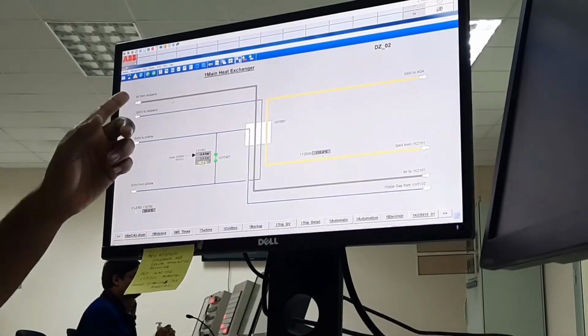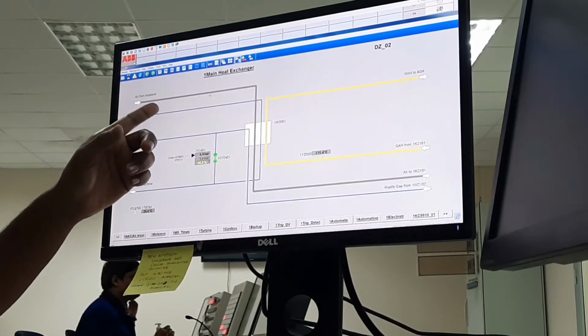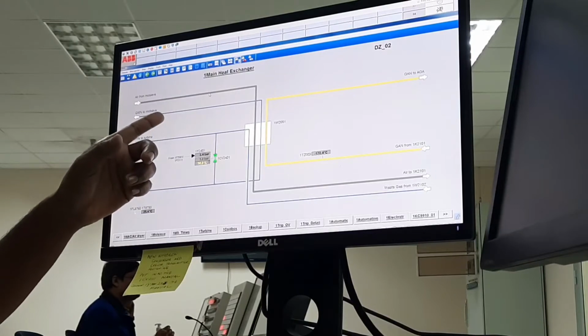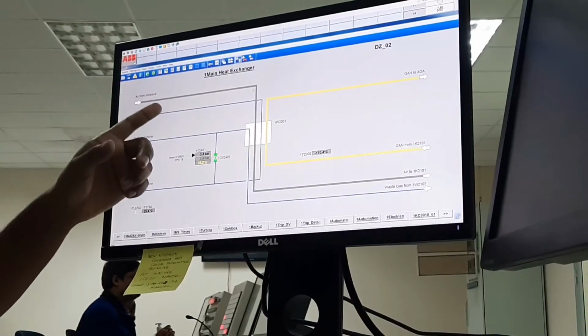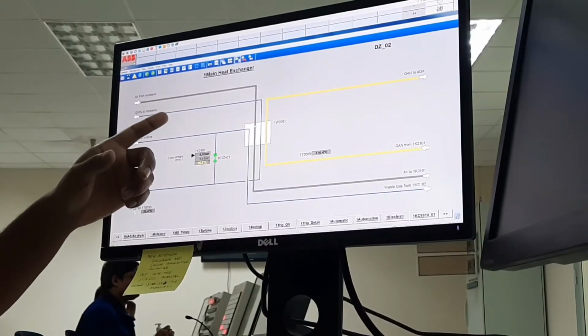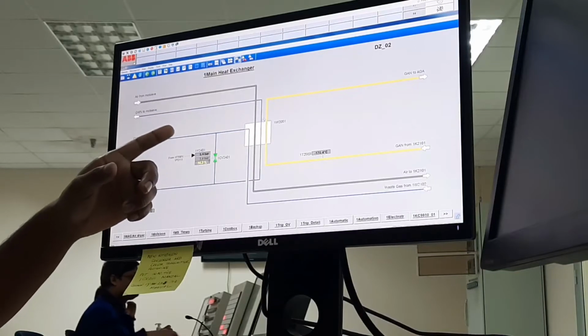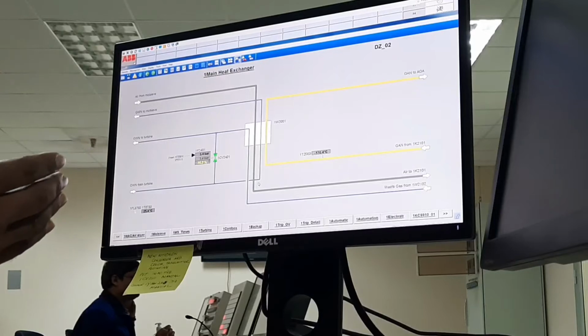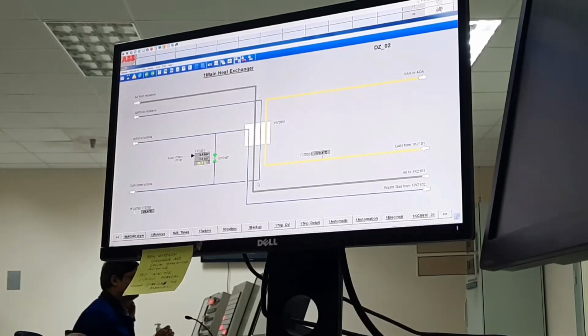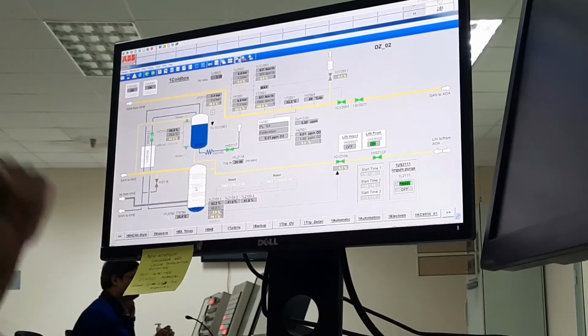Okay. So this is our main line: 1.2 kg pressure, 1000 normal meter cube air flow, 30 degree centigrade temperature. When it passes through the main heat exchanger, this temperature goes down. How much down? Around minus 168 degrees. After that, where will it go? The rectifier column.